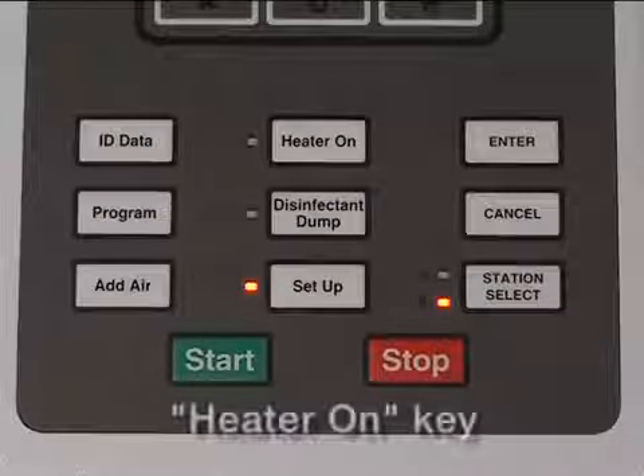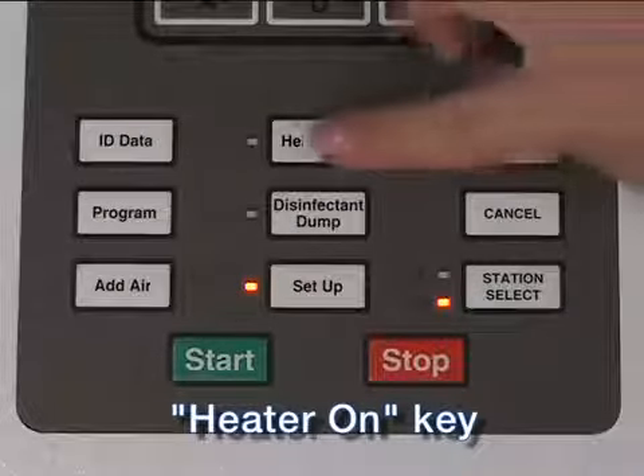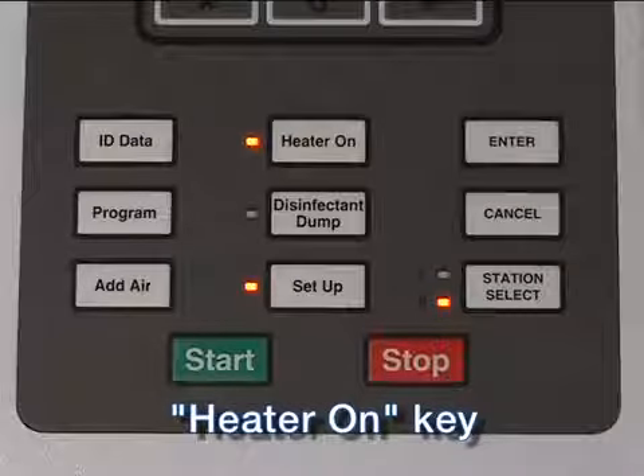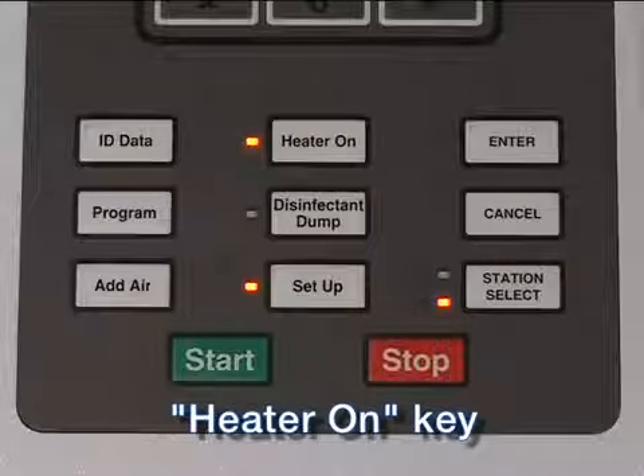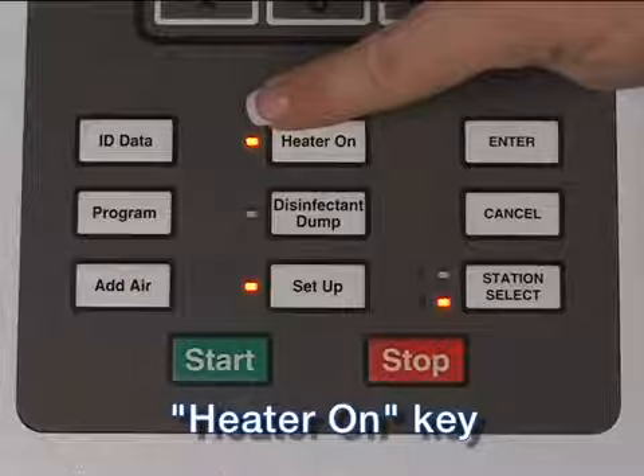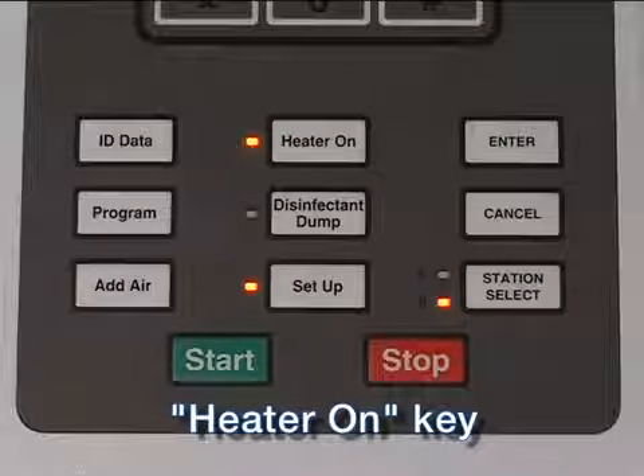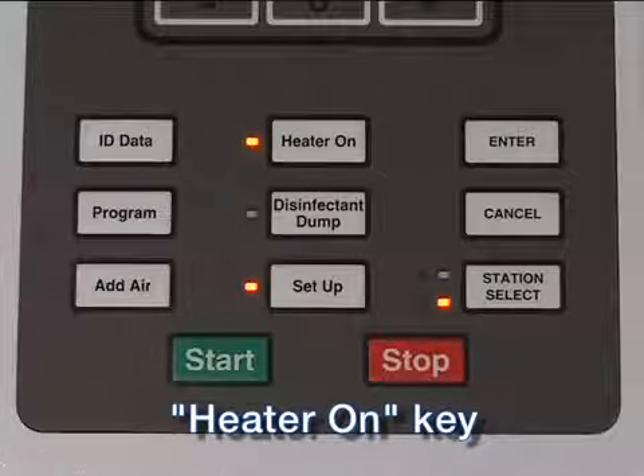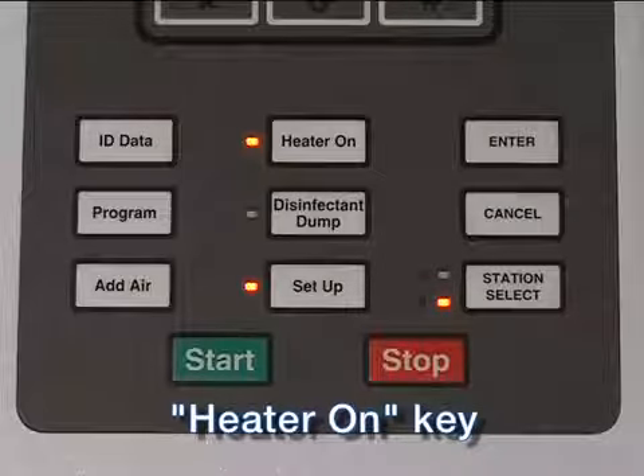Heater On key. Press this key to toggle the reservoir heater for the selected station, either on or off. The LED is lit when the heater is on. The heater should always be on when using a chemical that needs to be heated to achieve high-level disinfection.